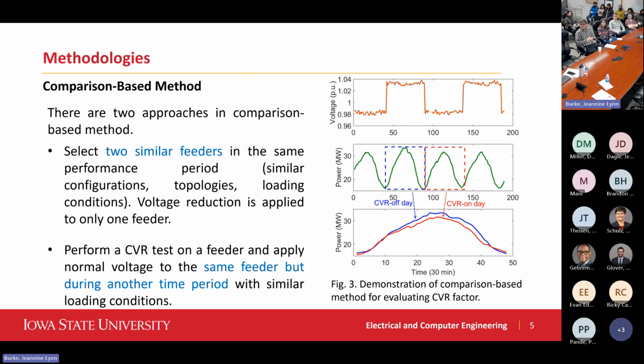Is that true? That's certainly not true. The reason is because you're talking about a 1 or 2% energy consumption difference, and the load is always changing, time from time. So the natural difference between the two time periods in terms of load may already cover up your 1 or 2%.